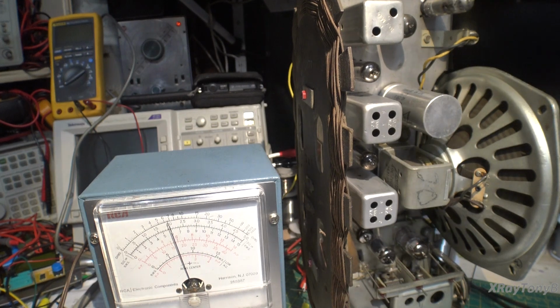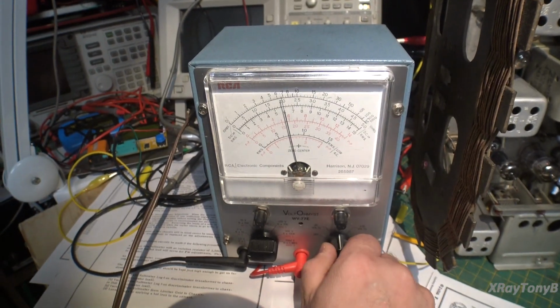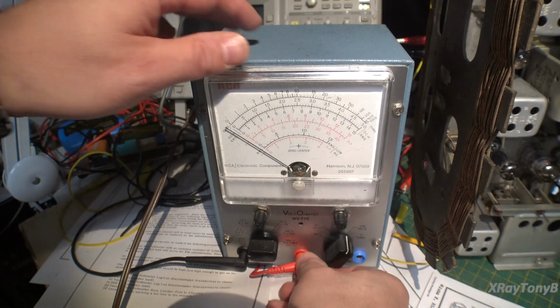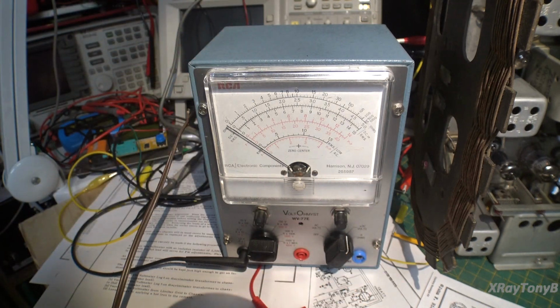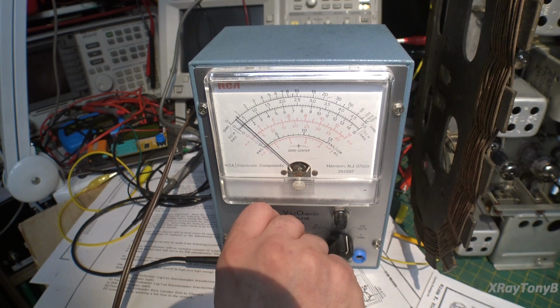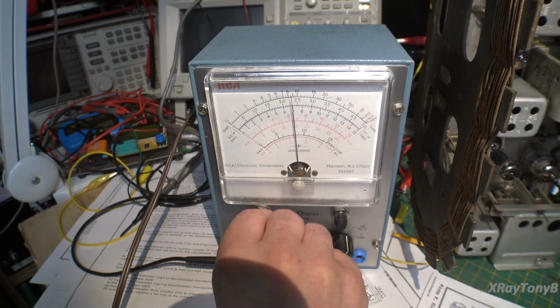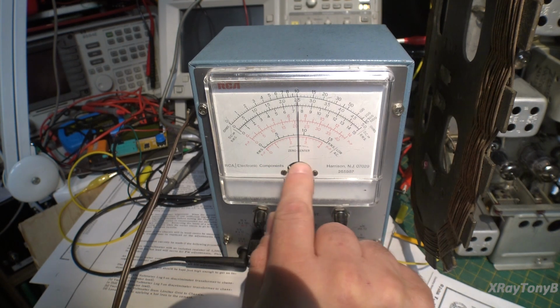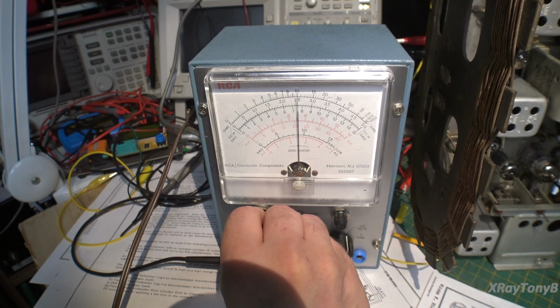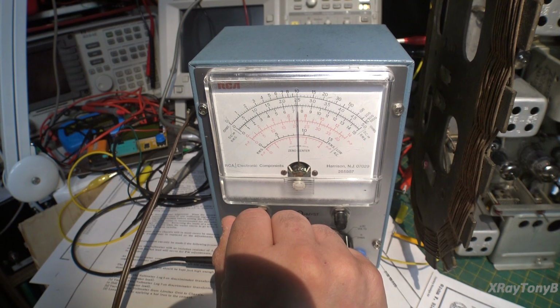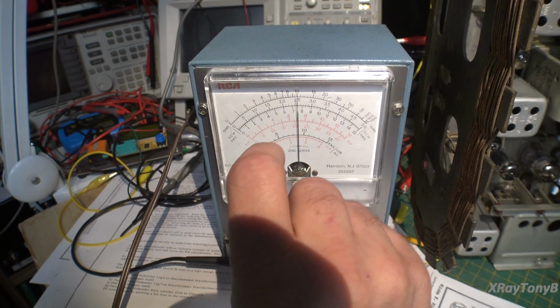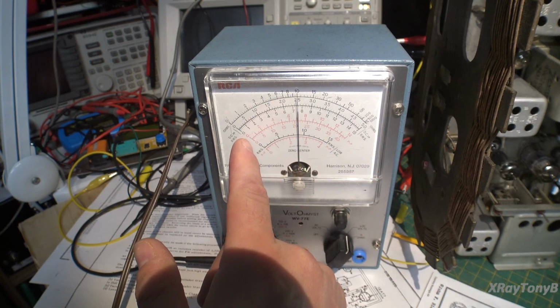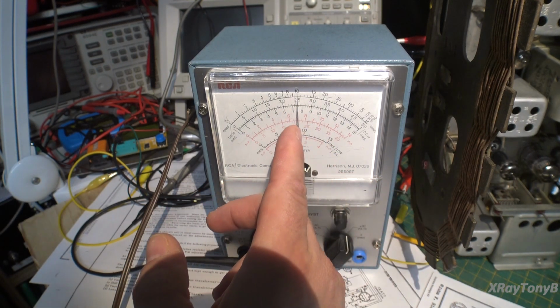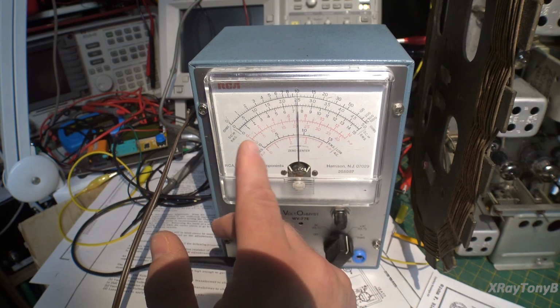Now to do a center read on a meter, you switch to DC volts, take the probe out for now so there's no voltage on it, and adjust the meter with the zero adjuster until it's centered where it says zero center. What that does is null the circuit out, so we want the circuit balanced at zero volts. As we adjust this slug, we can make it swing negative or positive, so this allows you to see negative and positive voltage changes.